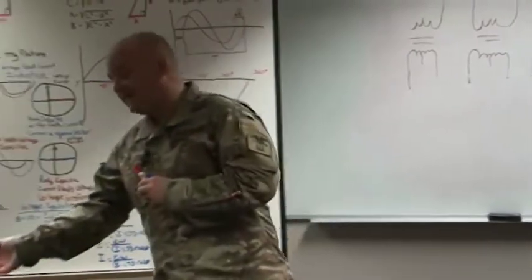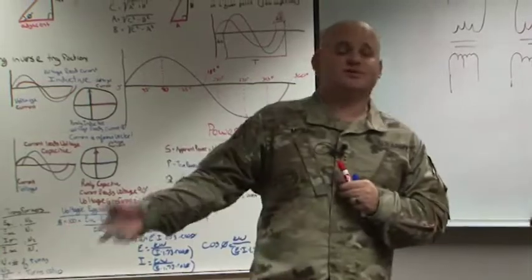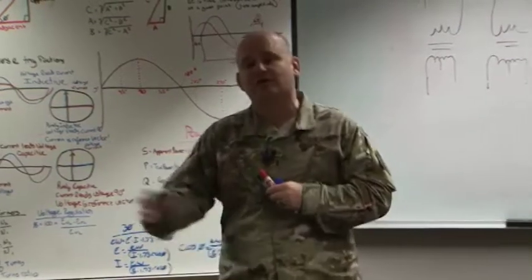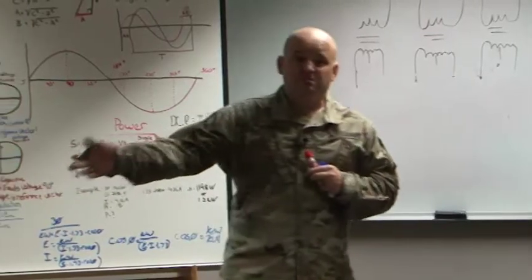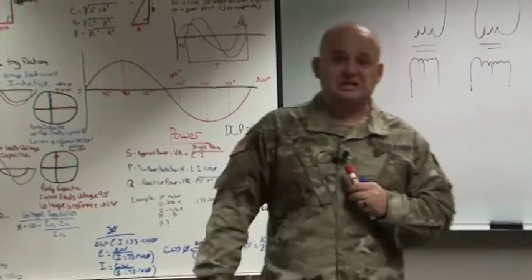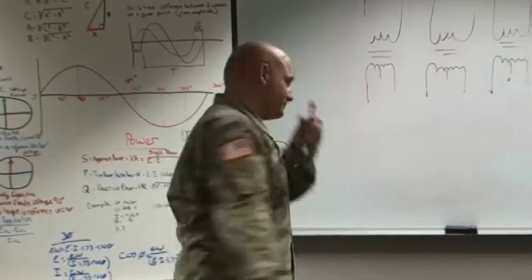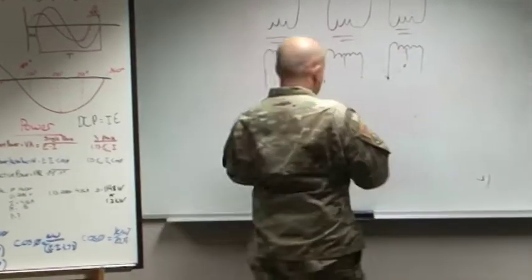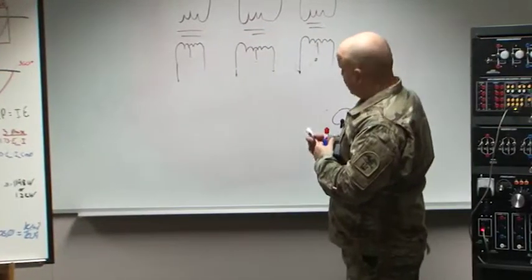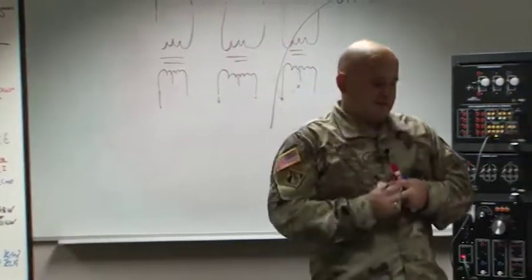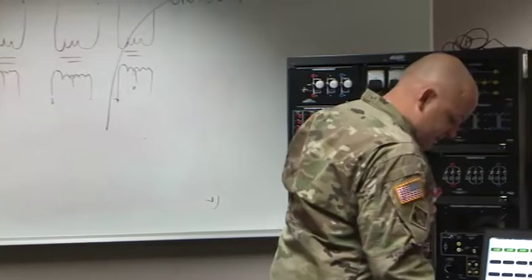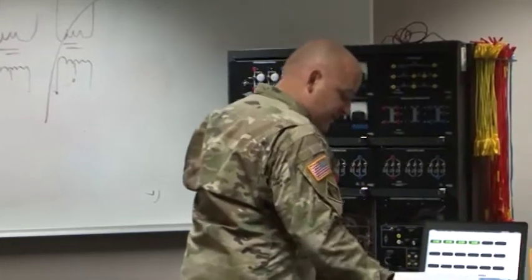The local utility has 2 transformers that meet the same requirements as far as the turns ratio, voltage rating, current rating, all that stuff. But I only have 2 of them. But I need 120/208, so I need 3 of them. I need that 3-phase voltage there. All right. So the open delta allows you to say, okay, delta, boom, I only need 2 of these, and I can create this same connection. All right. So how do we do that, though? How do we do that?